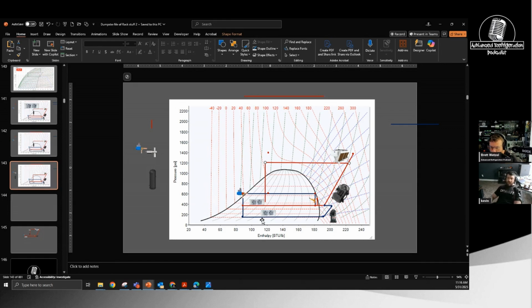I'd be interested to see what it runs on a hot day, but I had the condenser capacity cut down because I had the split valve down. That way I was running like 50%, so I was able to keep the fans still moving air across it, but we weren't getting a ton of subcooling.